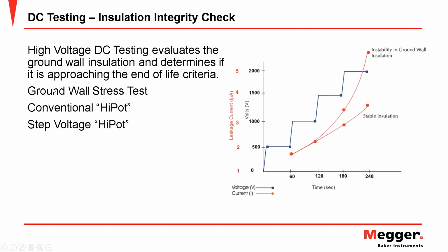So another, more illuminating, if you will, test is the step voltage test, which basically is the same kind of test, except we do incremental steps to test voltage. So we walk it up slowly and evaluate the leakage current at each of these steps and see if it has a very linear response. And so that's what we're looking for there. The linearity of that response basically lets me know that the insulation resistance is staying at a constant value throughout the test as I increase the stress. And that's what we want to see. If we start to see a departure from linearity, it isn't necessarily a test failure per se, in that it's not tripping on overcurrent or causing an arc, but we just start to see the nature of the resistance start to change its characteristic.